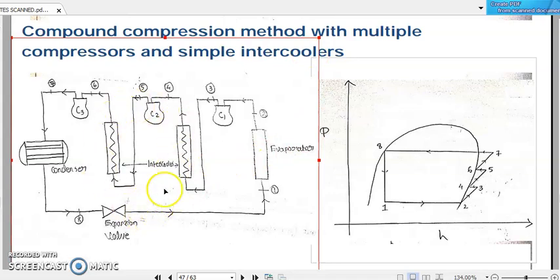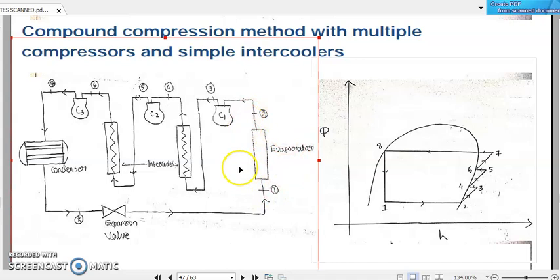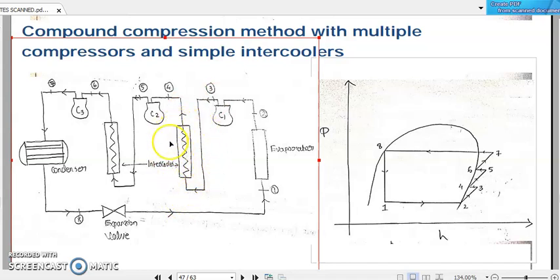Here we are discussing a multiple stage vapor compression refrigeration system. In this diagram, let us consider a simple arrangement where there is one single evaporator or freezer compartment, followed by compressors C1, C2, and C3. In between two consecutive compressors, we are keeping a simple intercooler. An intercooler is nothing but a simple heat exchanger where heat from the refrigerant will be rejected to another somewhat cooler medium.